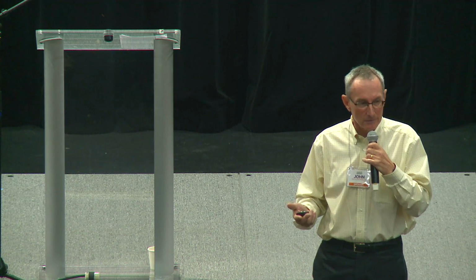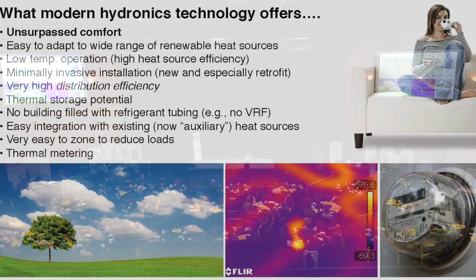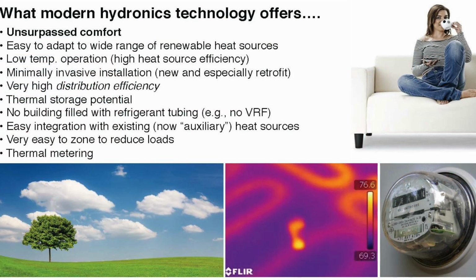And why is that relevant? I think sometimes our industry as well as consumers get so focused on thermal efficiencies, whether it's a COP or an AFUE rating. They get very focused on the performance of the device that's creating the heat and don't really consider the balance of the system. What's moving the heat? And again, hydronics, hands down, has the advantage there. We can integrate thermal storage. We can do thermal metering with it now. So there's a lot of things to like about hydronics, and these are all terms that we need to integrate as we build systems for these low-energy buildings.